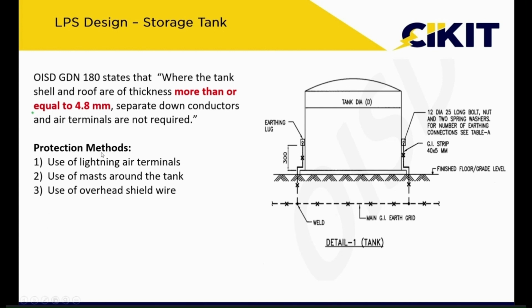So if the wall thickness is lesser than 4.8 mm, or if you don't want to take any risk and you want to ensure 99% protection, then we can go for any of the three protection methods stated by this particular standard. The three methodologies explained by this standard are use of lightning air terminals, use of mast around the tank, and use of overhead shield wire. So these are the three methods explained by this particular standard for providing protection for these tanks.